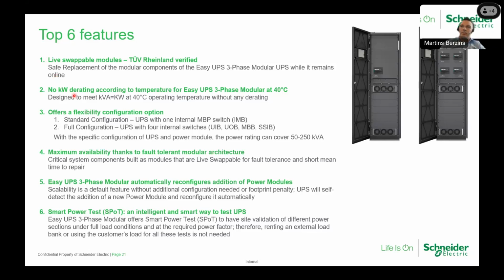UPS is a power factor of 1, so kVA and kilowatts equal the same rating, even at 40 degrees temperature. We have a flexible offer, so we have a standard configuration offer, which you can see here on the left side. Standard configuration means it has one internal maintenance bypass switch. So the UPS has one internal switch, or we have a full configuration with four switches for the maintenance bypass.